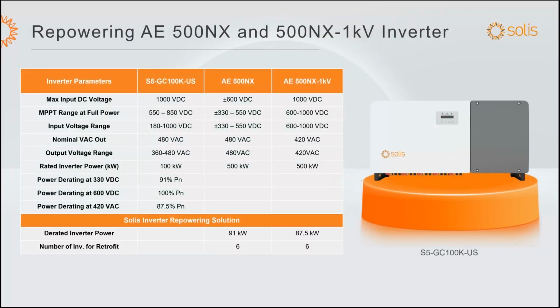So here we put the specs together of the same inverter, the 100 kilowatt inverter, S5 100 kilowatt, compared to AE 500 and AE 500NX. Similar point here, we're looking at the input voltage range. In this case, we can cover the input voltage range. Obviously, the plus and minus will need to split, and all will need to be a plus potential. So those need to be separated potentials, which is typical for an AE inverter.